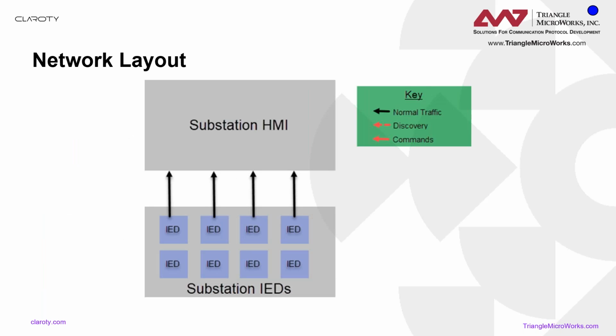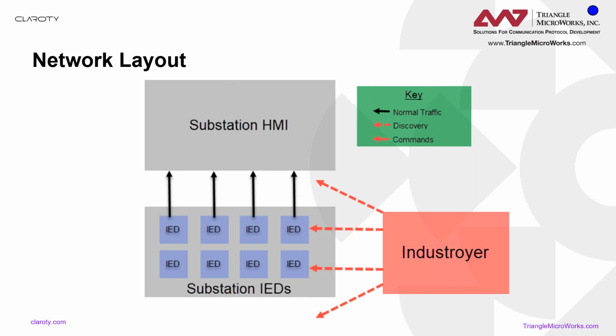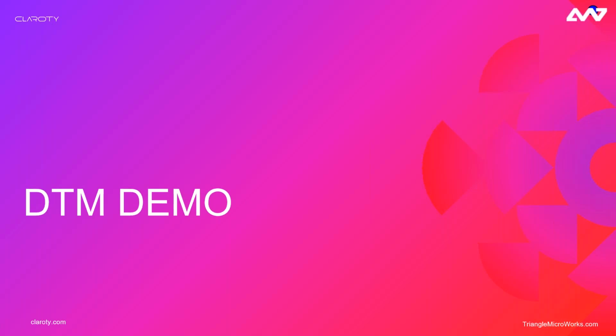So we've got our normal network layout again. Then Industroyer can enter the network via many routes. For example, it could infect the substation HMI. Then it'll start looking for IEDs to attack via ping and 61850 discovery. Once the IEDs are discovered, it'll issue commands to control certain points, such as breaker or switch positions. So now we're going to pause here and look at DTM a little bit. I'll give you a quick overview of DTM and show you exactly how we simulated that in DTM.